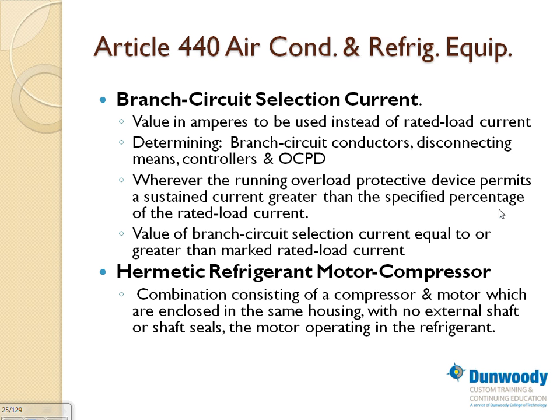Okay, any motor that has a compressor with it, when you couple a motor with a compressor, they act differently. So the people smarter than me lump them together in an article called 440, air conditioning and refrigeration equipment. Because of the refrigerant cycle in this equipment, they act completely differently. A fan blower is completely different than a compressor. So they act differently, and they go together. There's a couple of concepts you guys have to know. They call it branch circuit selection current.